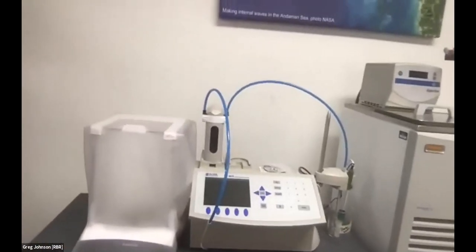Although she mentioned having reference optodes, our oxygen calibration is typically done against transfer standards. But just like with the super thermometers, we need to calibrate those transfer standards on occasion. We do that with Winkler titration. We have a small titrator here and scales, and that would be done once a week just to ensure that there's no drift. But once a year, we do a full Winkler over all 49 points, or 42, whatever it was. That takes quite a long time to do, because a Winkler is a slow process for those of you who know it. So that's something that we do routinely to make sure that we have real traceable standards going back to the very beginning.